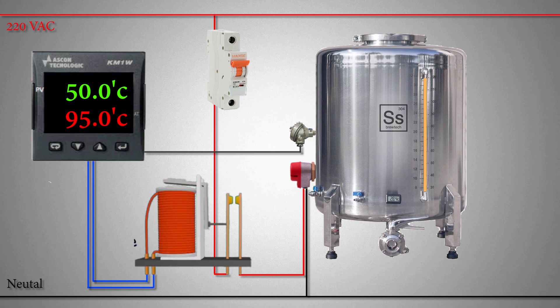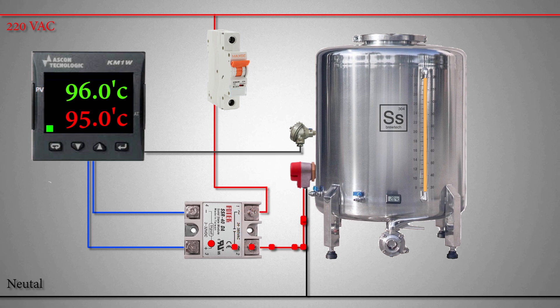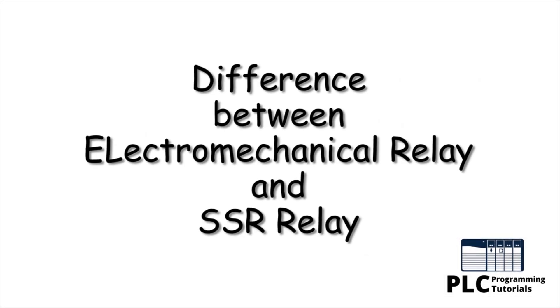Coming back to our tank heating example, we can replace the electromechanical relay with the solid state relay. As the temperature controller applies the control signal at the input of the SSR relay, the SSR relay triac starts to conduct electric current through terminals 1 and 2, and the heater turns on. The temperature in the tank gradually rises. As the temperature reaches the set point of 95 degrees, the SSR relay stops conducting the current. In this way, the temperature controller can regulate the temperature in the tank.